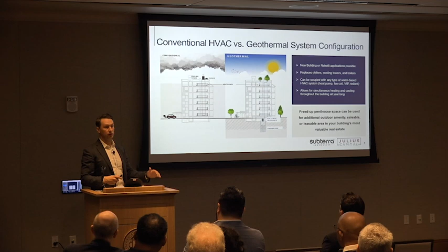Another key feature is simultaneous heating and cooling, meaning geothermal can take heat from one spot and move it into another space. Consider a data center, which always rejects heat and always needs cooling. Normally we pay to evaporate that heat into the atmosphere. With geothermal, you can take that constantly rejected heat and use it to heat an adjoining space, like a residential dorm or apartment that usually wants heat, especially in winter. You transfer that heat for free, which is a great application for campuses with diverse loads.